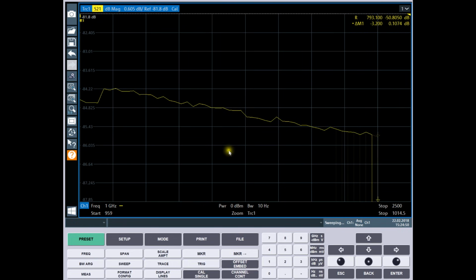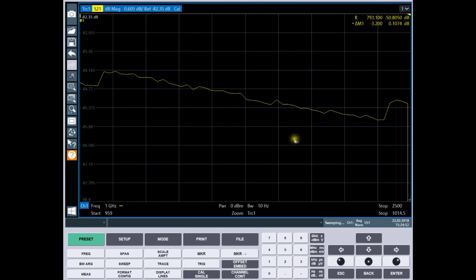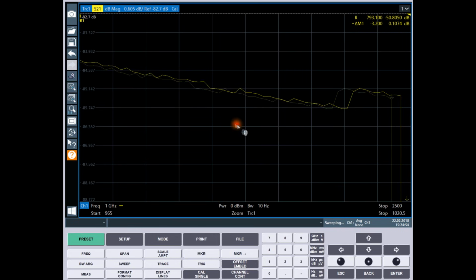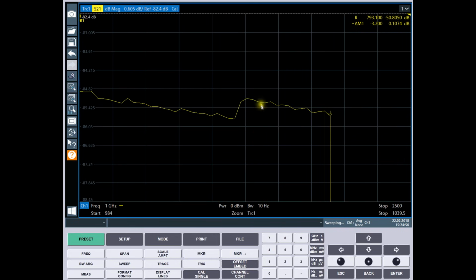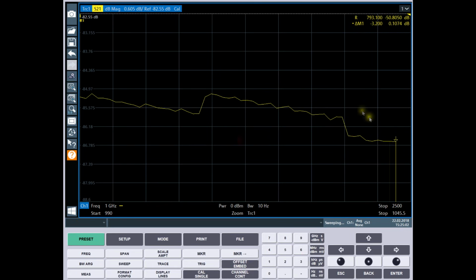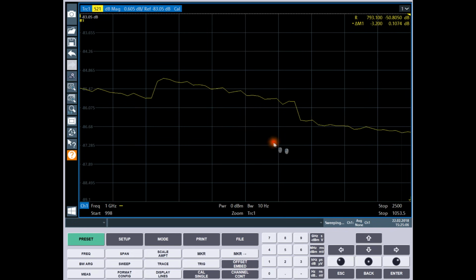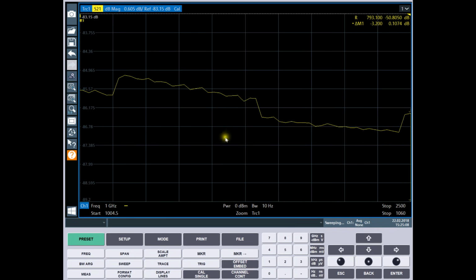You can see that we're beginning to lose some of the accuracy of the steps, but the trend is really still visible. For example, we know this jump should be about 0.5 dB, and we verified that it is 0.5 dB, and there you go. Here's a mistake again from the attenuator, as you can see. So clearly that problem is still well visible here.